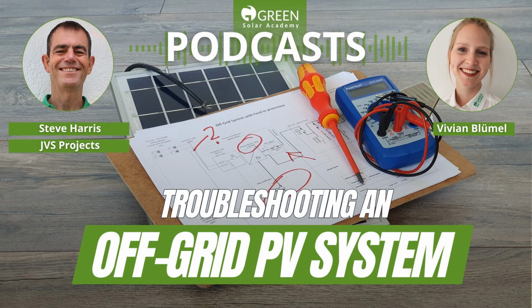It's been my experience that people generally have been oversold on what their systems can do. They say it can do this, that, and the other thing, and when you look at what's been installed, it's not capable of doing it - probably capable of something in absolute optimum conditions. But for me, mostly when a system is underperforming, it's because it's been under-equipped - either the batteries are too small or there's not enough PV generation going on.